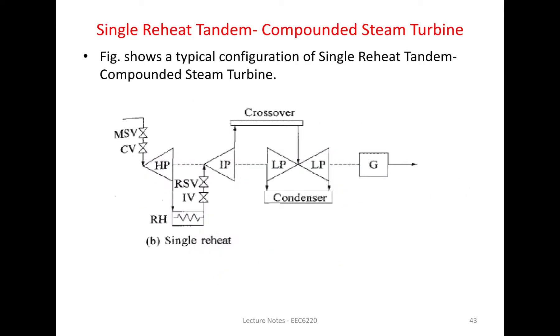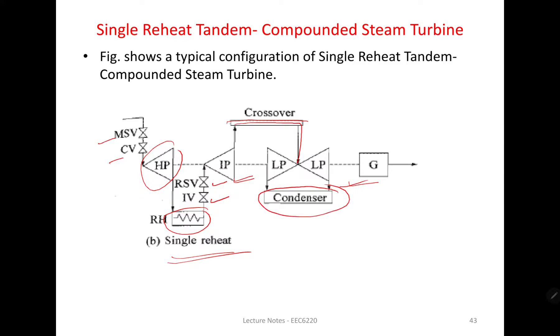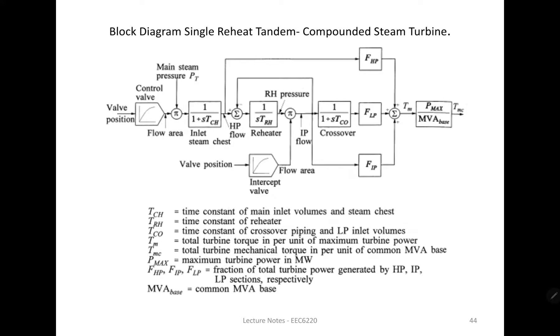Now, considering the single reheat tandem compounded steam turbine: in this system there is a main stop valve MSV, a controlling valve CV, then the high pressure turbine, followed by reheating, then a reheat stop valve RSV and an intercept valve IV, then the intermediate pressure turbine. After the crossover, steam goes to the low pressure turbine. All these turbines are connected to the generator, and the remaining steam from the low pressure turbine is condensed.